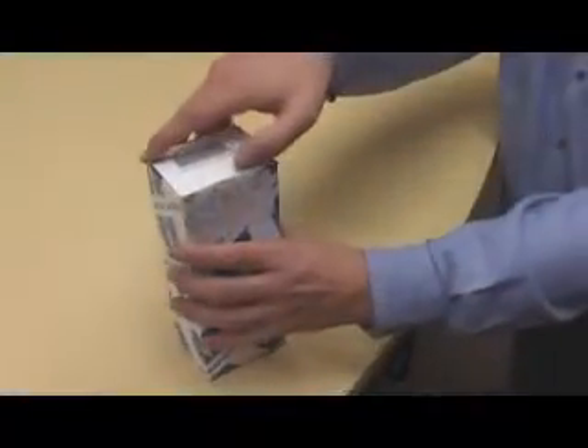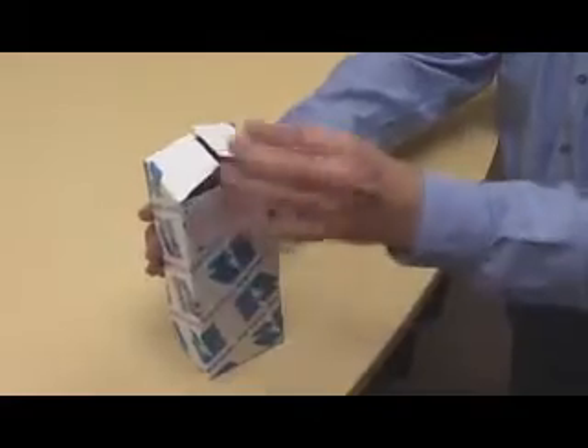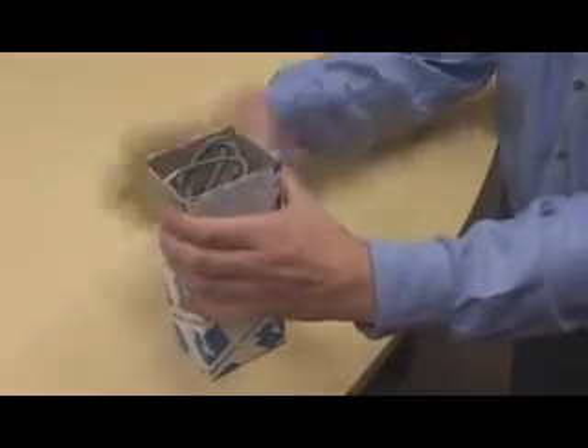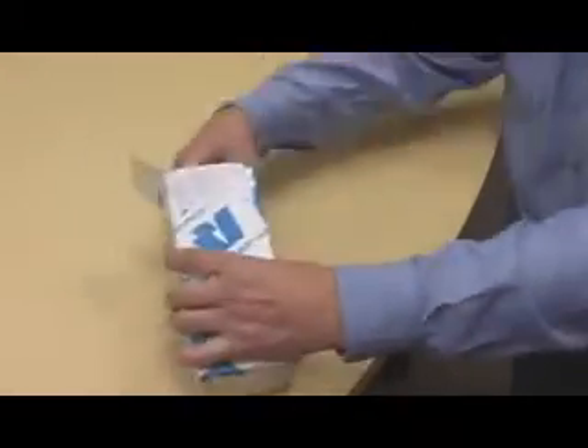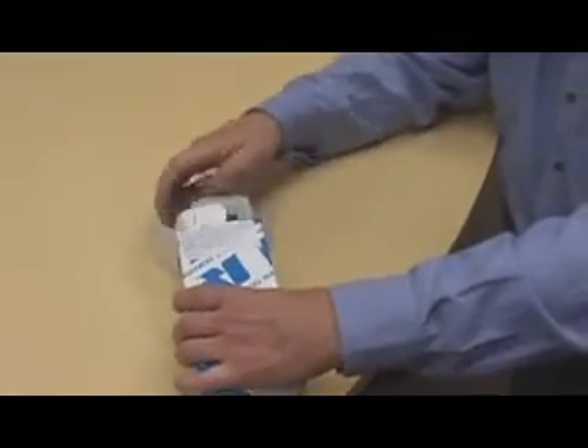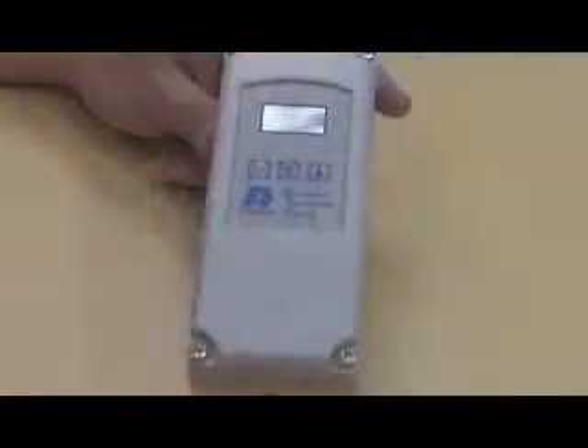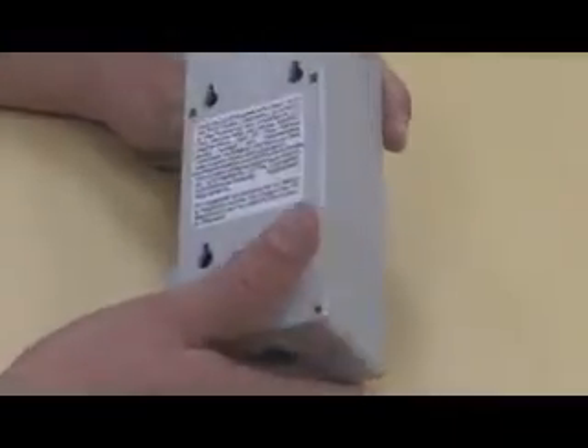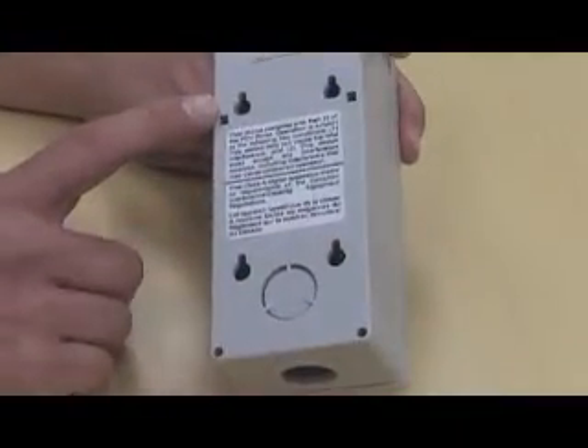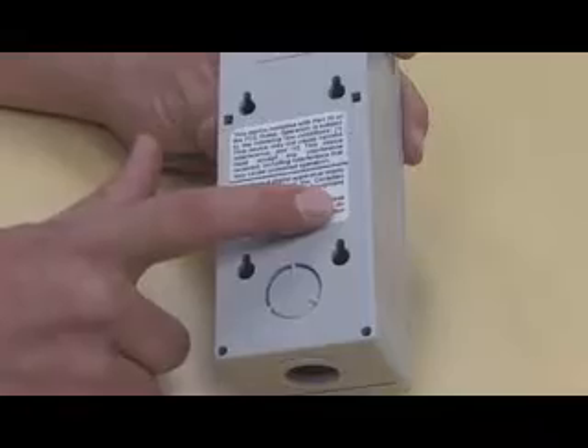How to install your ETC. There are three major components to review: physical installation, electrical connections, and simple programming to set your electronic temperature control. Let's review the installation steps now. Physical installation is designed to be a quick process. 1. Start by mounting the unit to a flat, clean surface using a combination of any two or more of the slotted holes located on the back of the control case.